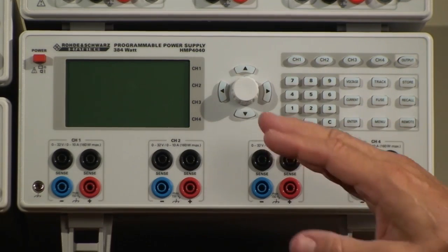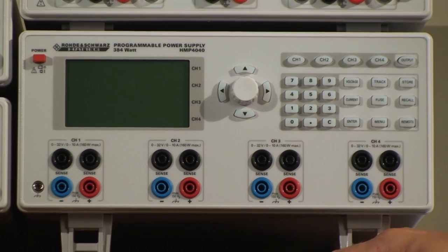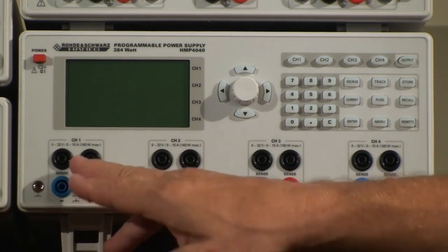This is the Hameg programmable power supply, a four-channel programmable power supply capable of delivering up to 40 amps, 10 amps on each of the channels with a maximum of 32 volts.